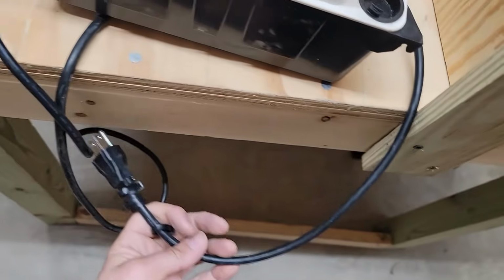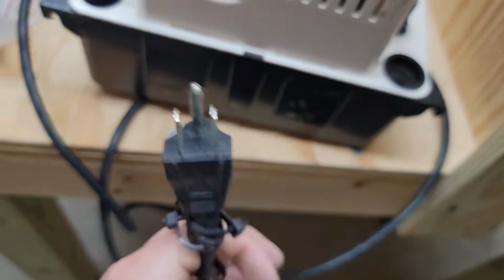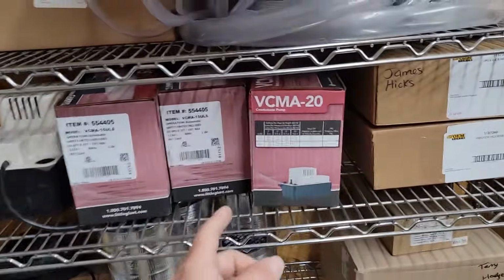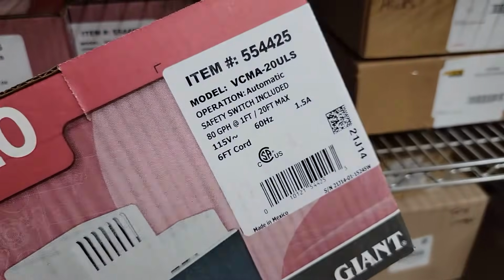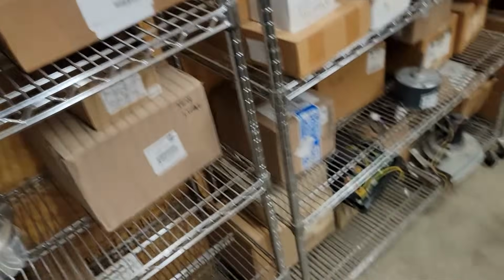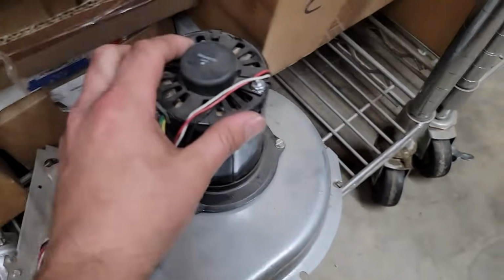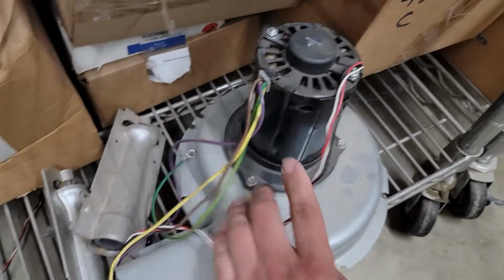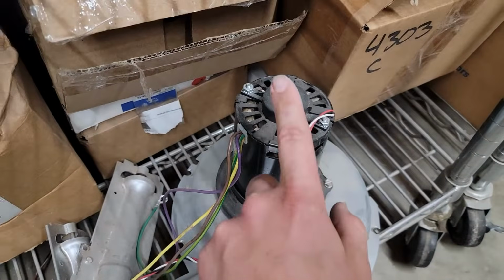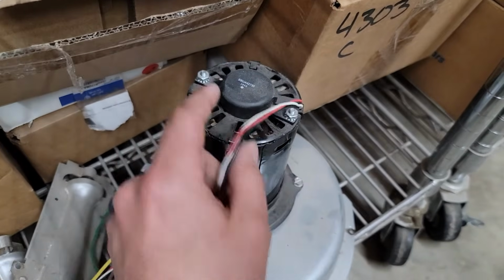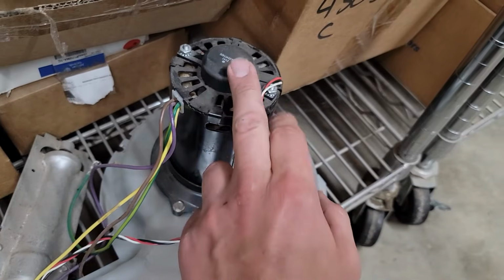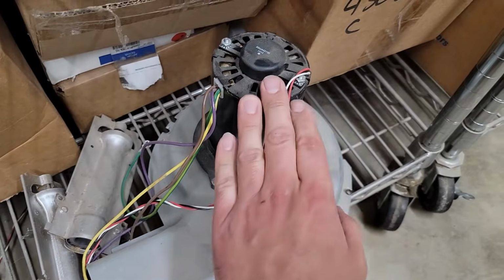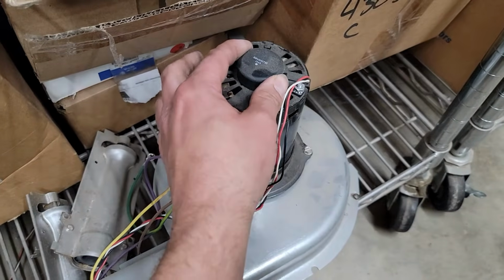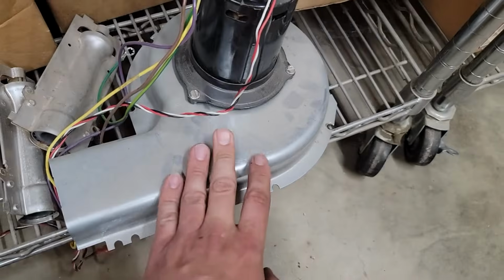You may need this. There are 120 volt condensate pumps like this one, 120 volt. And then there are 230 volt condensate pumps. I don't know if we've got one or not. Nope, that's 115. All right, this is an inducer motor. It's got a Hall effect sensor on it, so it doesn't use a pressure switch. And this is for Carrier. Carrier, I think, is the only brand that has these Hall effect sensors. Whenever the motor runs, this sends a signal back to the board, letting it know the inducer motor has proven that it is working. So I wanted to show you that because not many people know what this is, but this is a Carrier inducer motor.